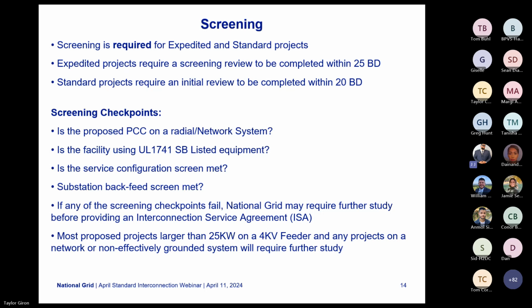We also check radial and network systems, make sure that all the required listings for all the equipment are UL 1741 SB, and then do substation backfeed screens, 3V0 screens, anti-islanding or islanding screens. If any of those checkpoints fail, they need to proceed to impact study for further detailed modeling.